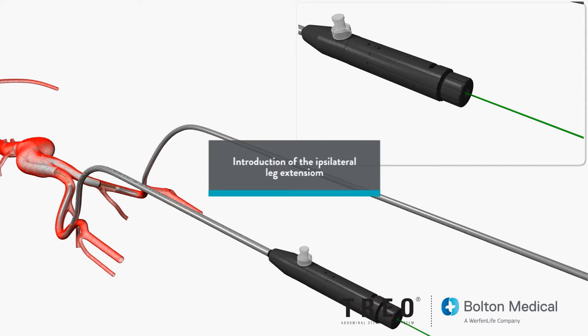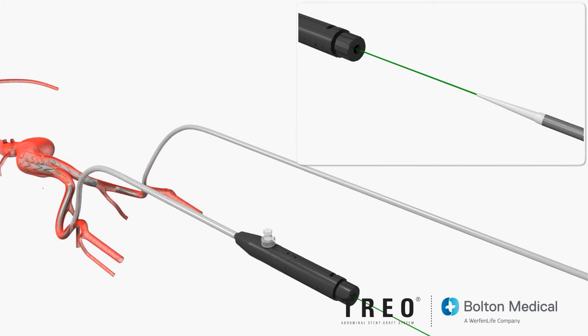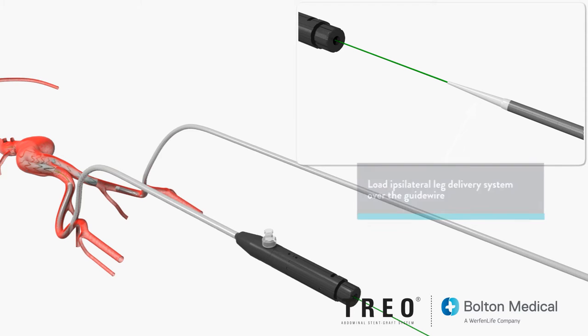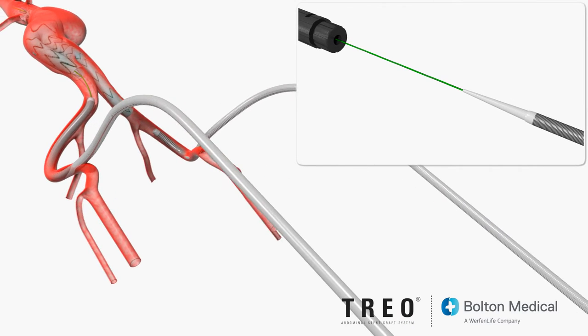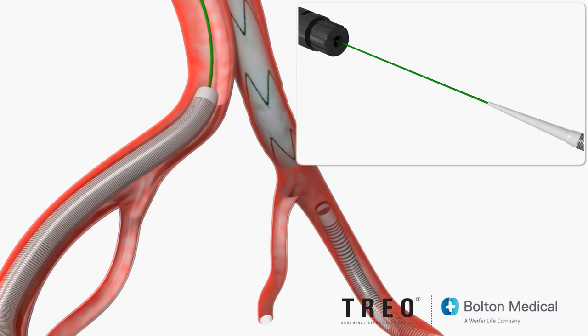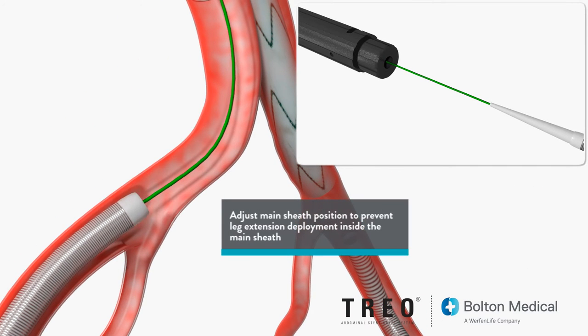While holding the sheath hub assembly with one hand, advance the ipsilateral leg delivery system over the wire until the tip of the delivery system touches the main sheath hub assembly. Adjust the main sheath position to prevent leg extension deployment inside the main sheath.